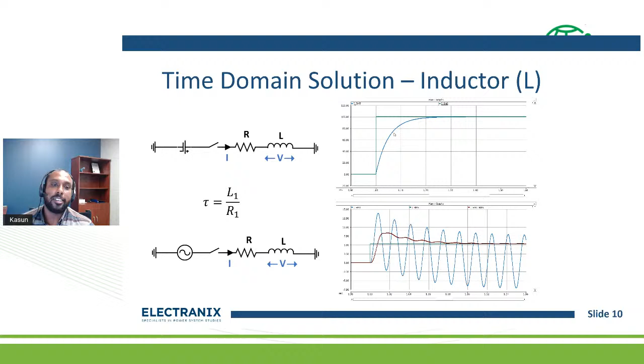Similarly, if you energize with a sinusoidal waveform, in the RMS based tool you have a step response kind of behavior, while in the EMT based tool you have a slight overshoot before it settles to the value seen in the RMS based tool. This initial transient, or the initial behavior of the current or voltage, is the key thing in transients. When we lose this behavior, we lose many things we should have seen. That's the main idea of why we need EMT studies.